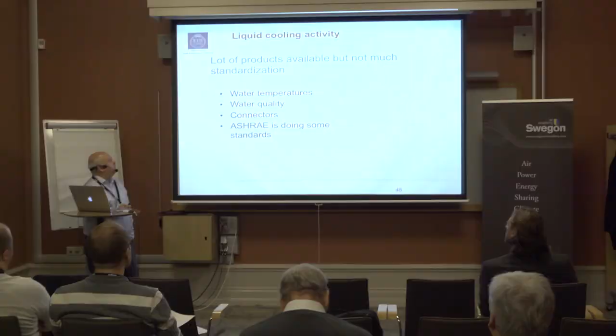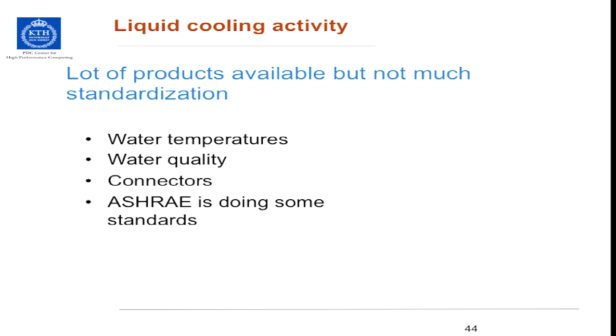To summarize: liquid cooling is coming fairly strongly, and there are a lot of products available today, but not much standardization — we lack standards for water temperature, water quality, and connectors. ASHRAE is doing some standards work, not only on temperature but also on water quality, and they have a lot of white papers worth reading if you're going into liquid cooling. I can recommend that.